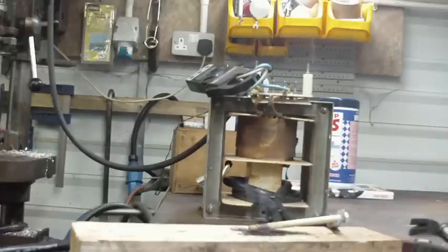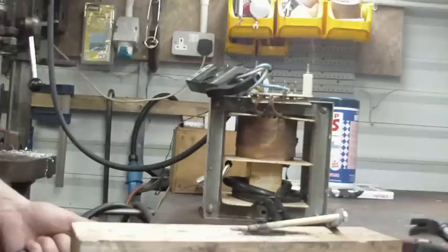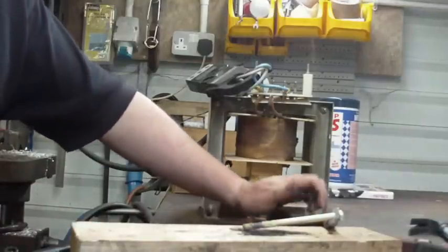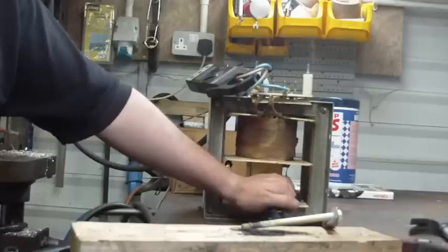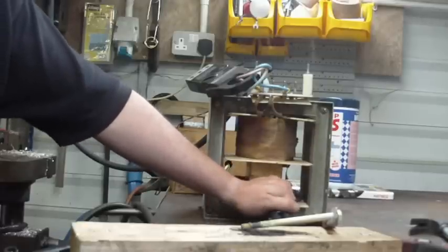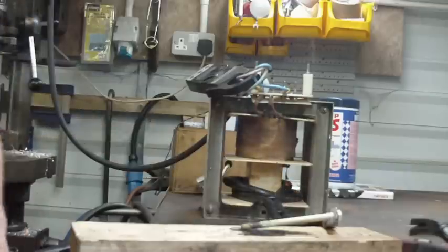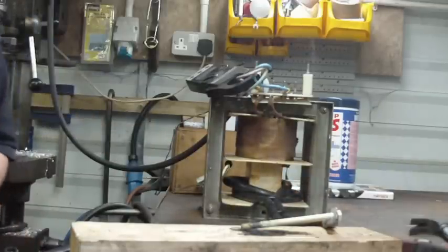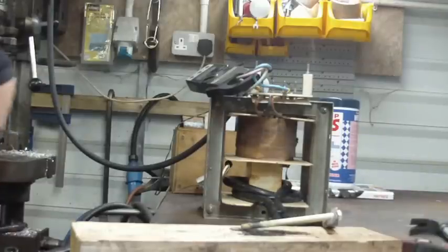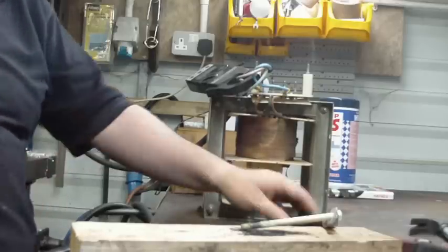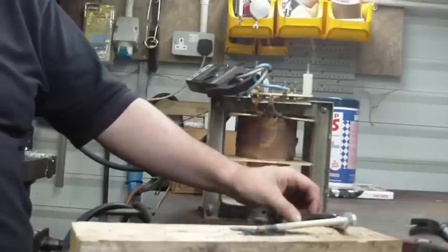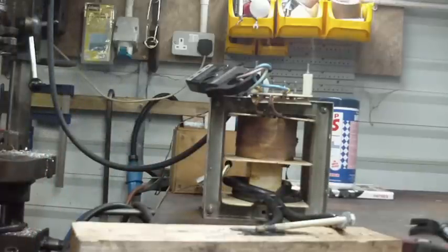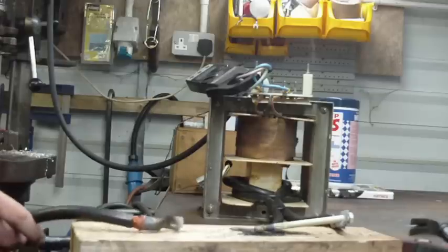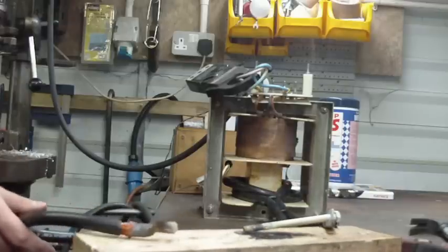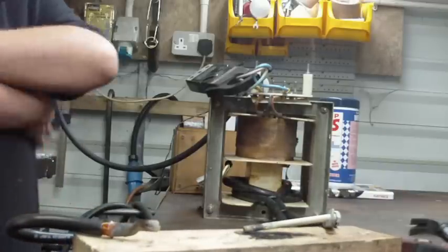Okay, that is power off. Let me get a feel of that 70 with my bare hand. Yeah, it's, whoa, I think it's actually not too bad in here at the core, maybe 40, 45 degrees C, but up nearer the ends it's getting serious. So what I'm guessing is actually happening here is that our copper is heat sinking the heat. Oh, it's melting the insulation there. Our copper is actually sinking the heat out of the actual test piece and drawing it back up the cable.